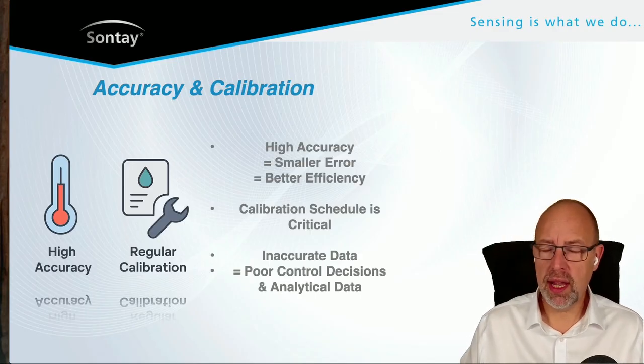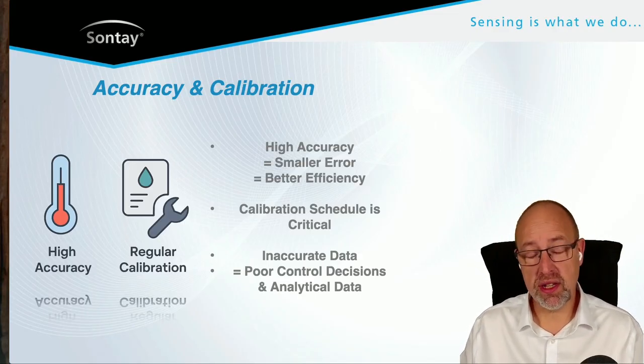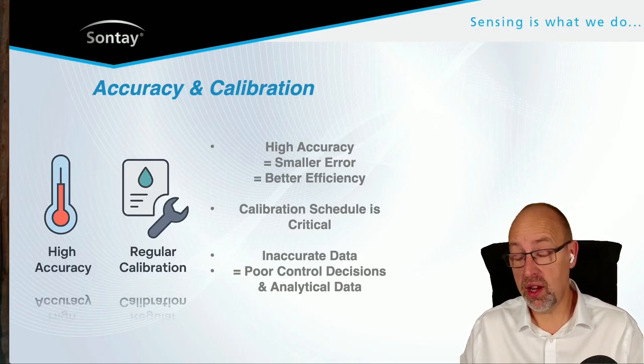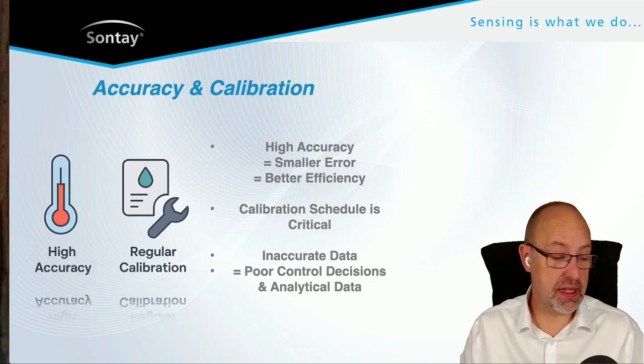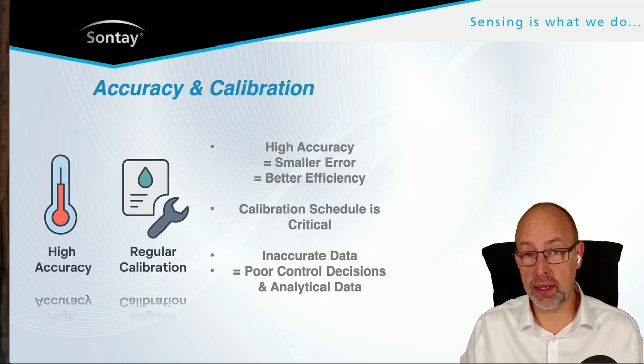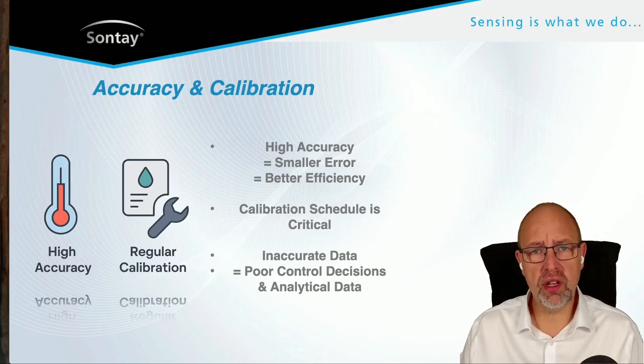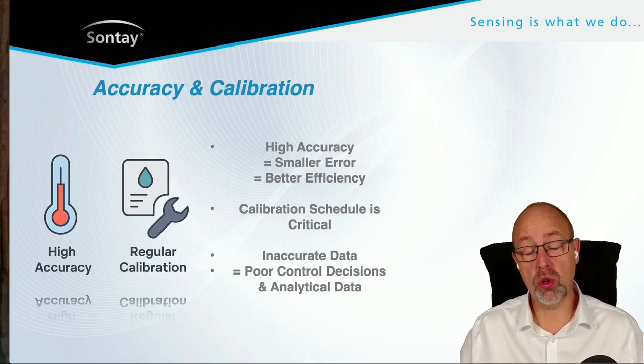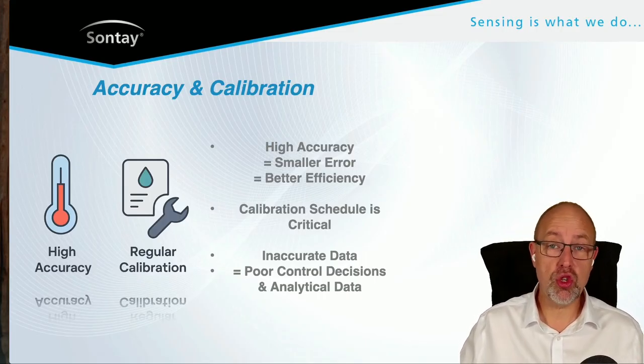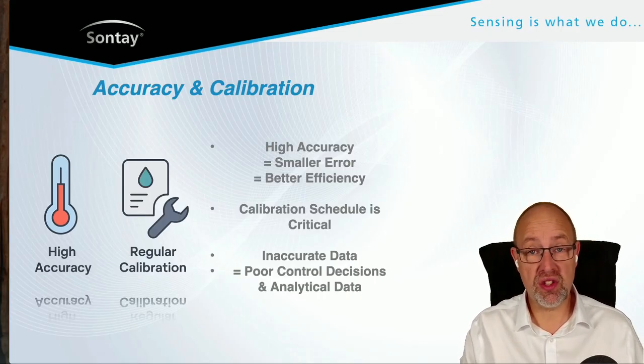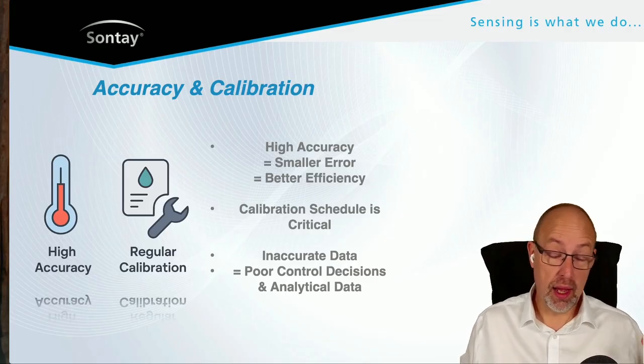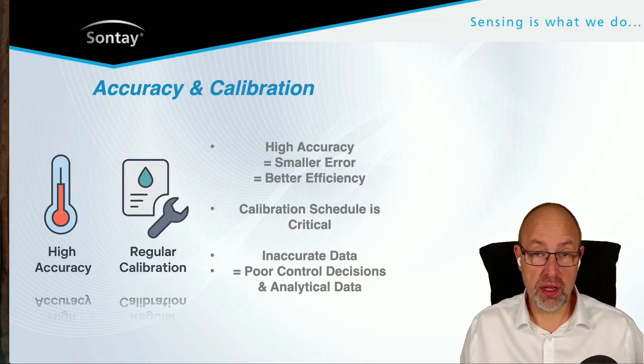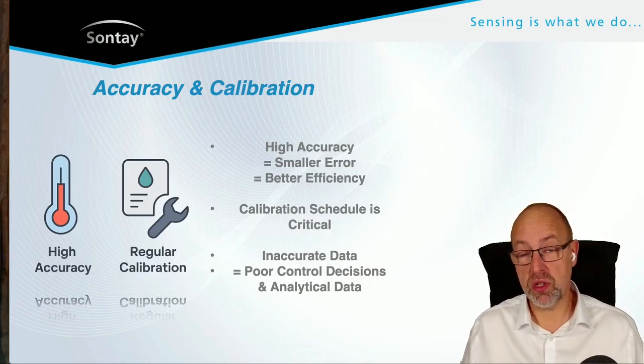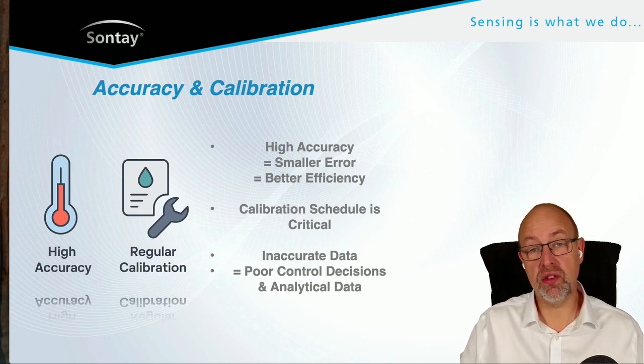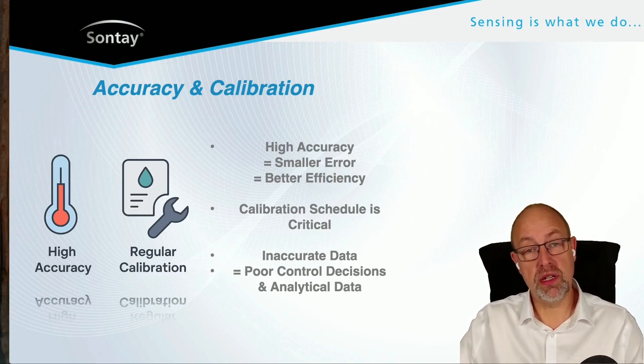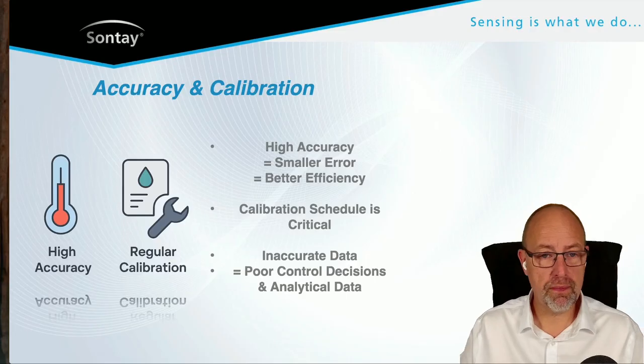If you've got something with electronics in it, so if you've got an active sensor with some electronic components in it, or a relative humidity sensor, a pressure transducer, something like that, there's a lot more that can affect those sensors. So you want to check them regularly and make sure that there is a scheme in place for recalibration. Very often that would need sending off site, so you need replacements on site so you can replace that device with one that you know is calibrated and send the other one off for calibration.